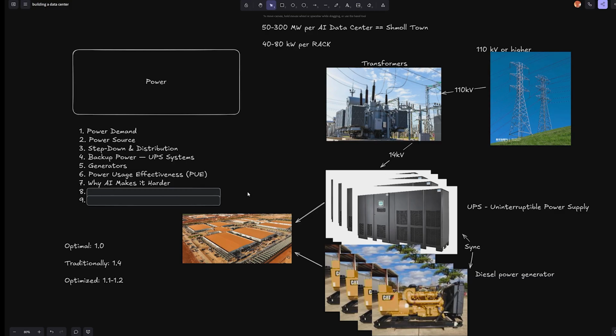Why does AI make everything harder? GPUs still pull power in sudden surges, aka burst loads. Power systems must absorb those fluctuations without voltage drops, and dense AI racks can exceed cooling limits, forcing higher PUE or liquid cooling. Everything in these systems is tracked: voltage, current, temperature, and there are real-time alarms tied to all of this. Automatic load balancing keeps critical paths stable if one feed fails. As I mentioned earlier, the cost of a failure or an outage is multiple times the cost of having backup ready and running. There are many challenges associated with setting up a data center.